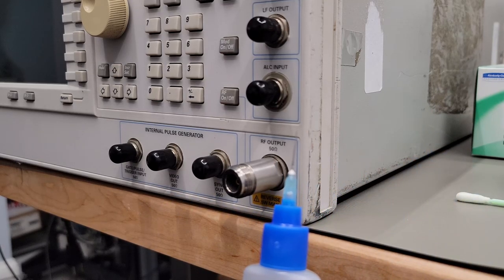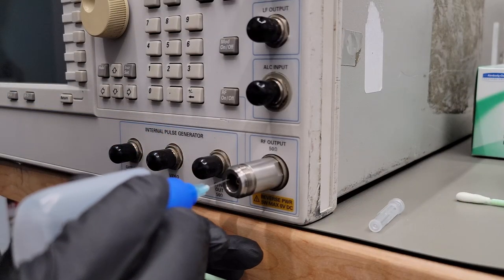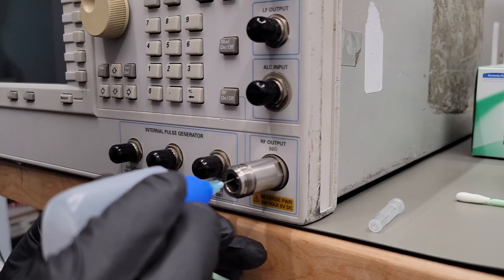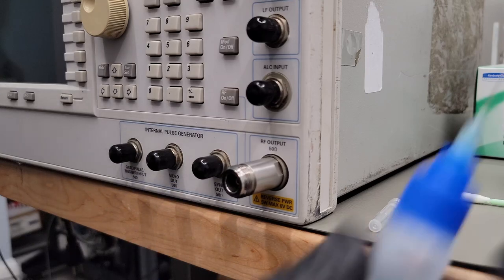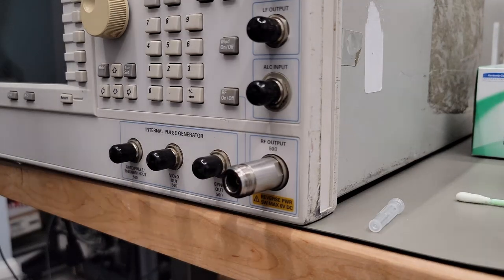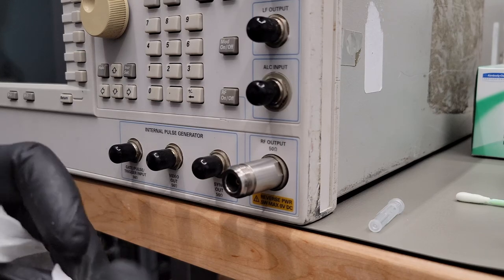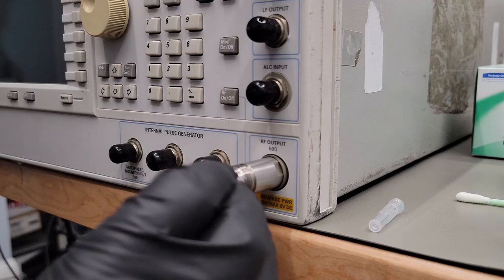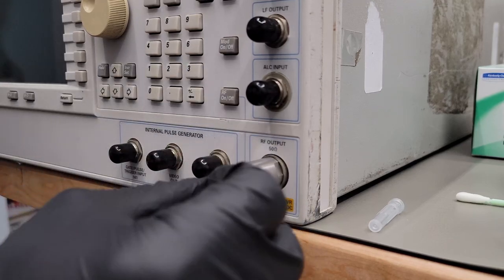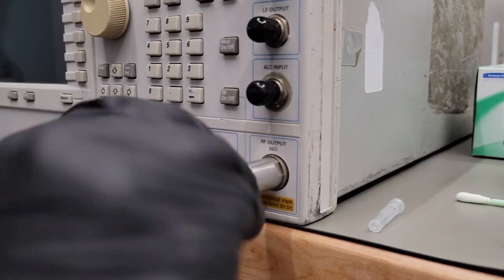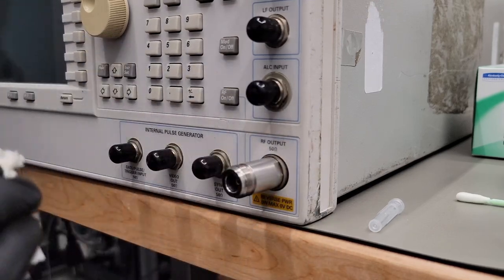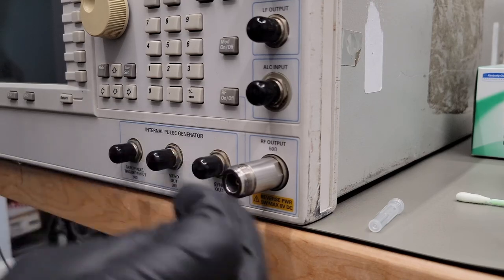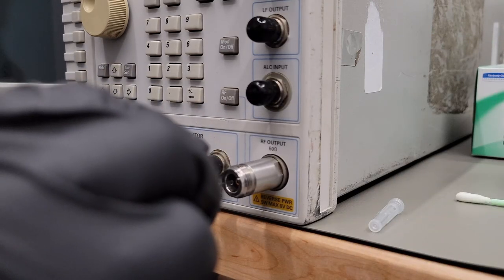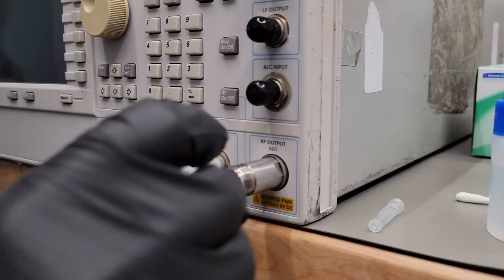Okay, so now that I'm pretty confident that the outside is relatively clean, I'm going to go ahead and use my needle applicator here to carefully apply some alcohol inside of this connector. So I'm going to drip it over the center conductor, and it's also going to fall around the inside of the barrel of the connector. And then to start, I can start with a piece of Kim wipe and just kind of swab the inside, not forcing it in because you don't want to damage the center conductor, but just kind of swab the inside lip that's closest to you. Because you do get a lot of debris and dirt in that immediate area where the center of the mating plane is.